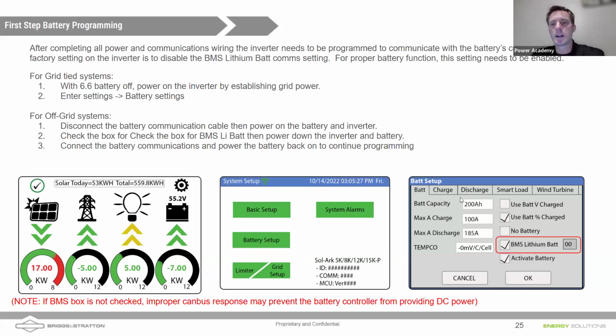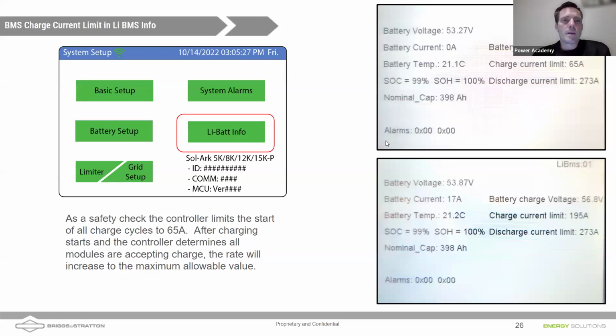There are ways around that, such as disconnecting the battery if you truly need to program directly from battery power. So once that box is checked, you should see an additional box show up in settings, and that's lithium battery info. So as long as everything is connected properly, you've got everything hooked up properly, you've got that box checked for lithium battery info, you'll see this additional green box show up in the settings menu on the Sol-Ark. And you should see some information like this, telling you information about the state of charge of the batteries, their temperature, the charge and current limits, that kind of thing.